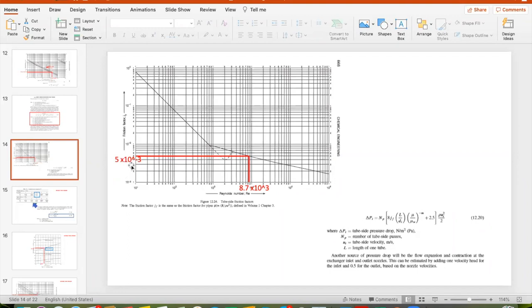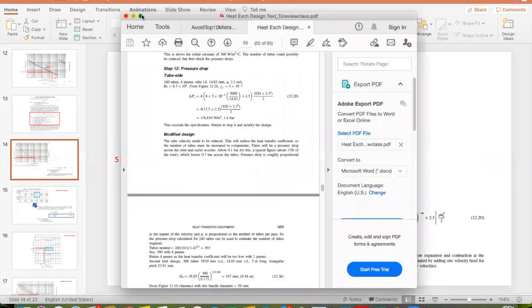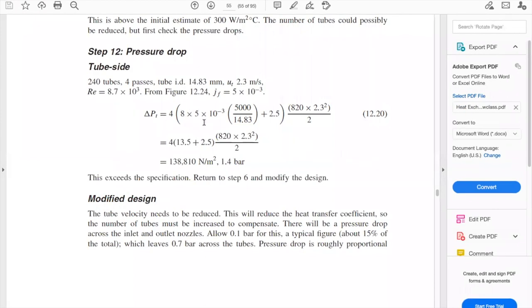These graphs are not very easy to read, but this is a very well-known textbook for design and the graphs are very accurate. Once we have the friction factor for the tube side, we can put numbers into equation 12.20. If we convert to bars to compare with the limiting pressure allowed in this problem, we find that the delta P in the tube side is 1.4 bars. Is this allowed according to the design requirements?